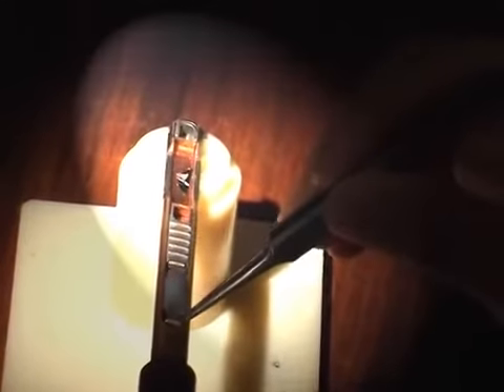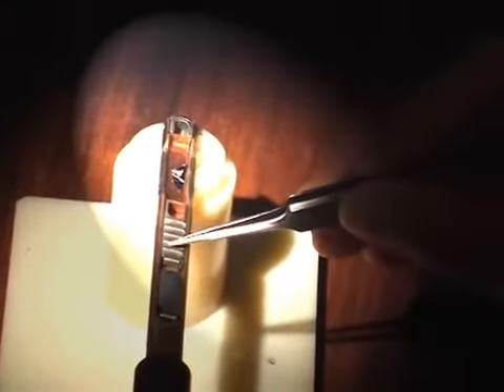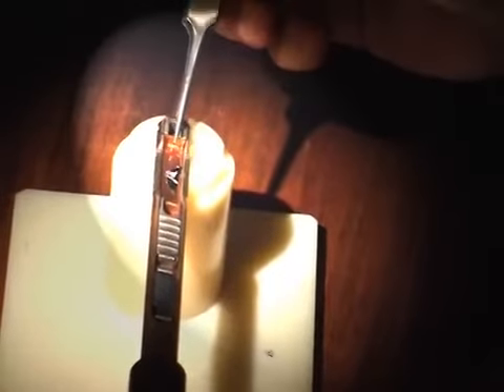Use fine forceps to place a new specimen stub into the end of the sample holder. Use fine forceps to push the metal release tab. The serrated metal clasp should jump forward, locking the specimen stub into place. Turn the sample holder upside down. Using a gloved finger, tap gently on the sample holder to ensure that the specimen is secure in the holder.